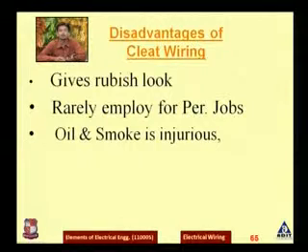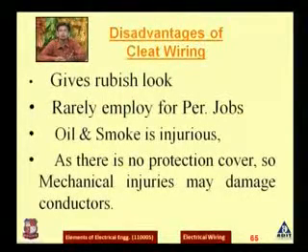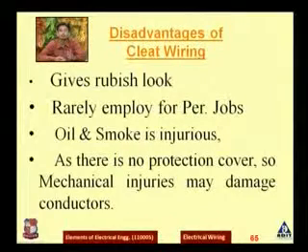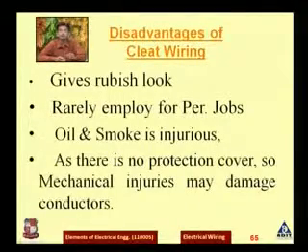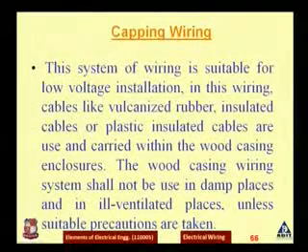Third, oil and smoke are injurious to the cleat wiring. So this cleat wiring cannot be done where there is smoke or in an oil refinery. Fourth, as there is no protective cover, mechanical injuries may damage the conductors. So the conductor will not be in a proper condition in the cleat wiring system. This cleat wiring system is not permitted as per the international standards. Now we will see the second method, that is capping wiring.